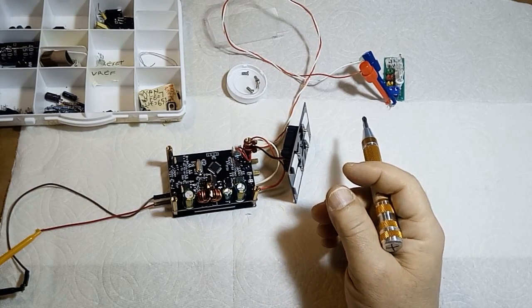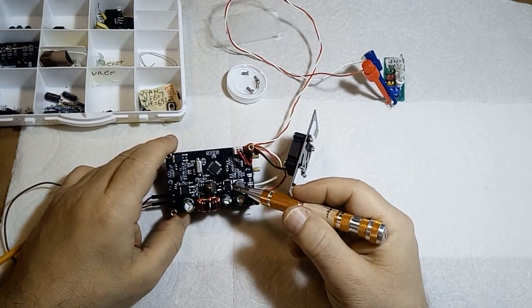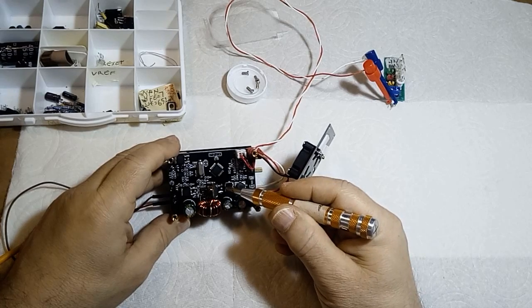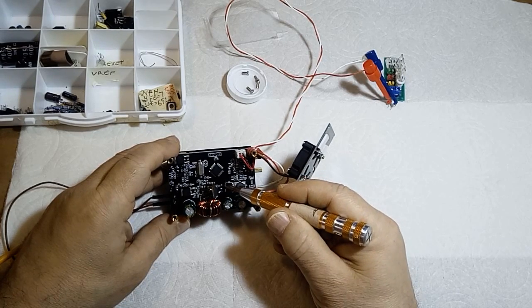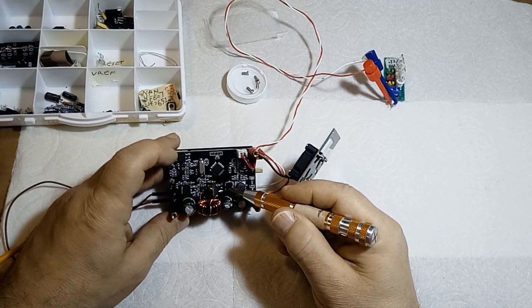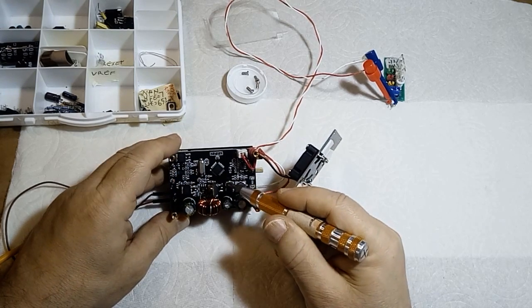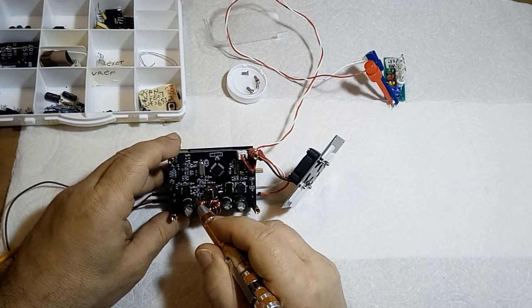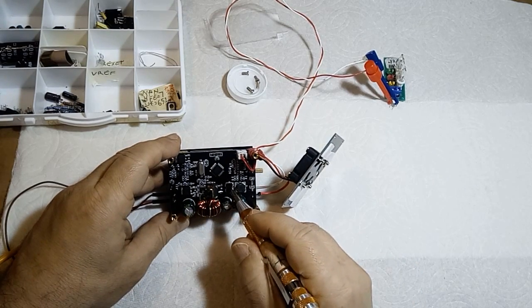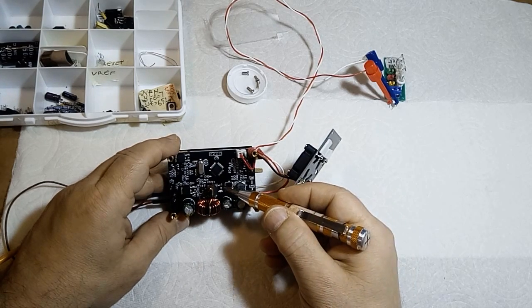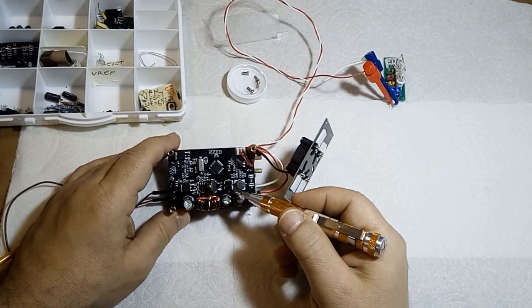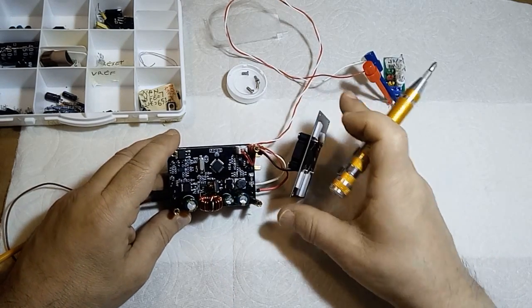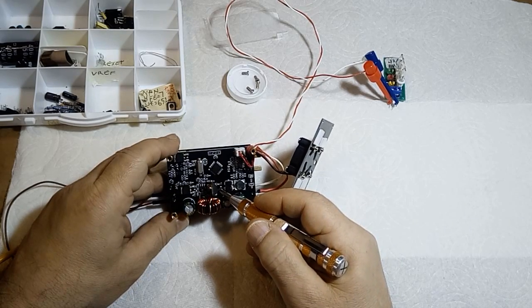I traced out the voltages and found where I got no voltage, and surprisingly where I got no voltage the component was hot, so it was obviously completely shorted out.